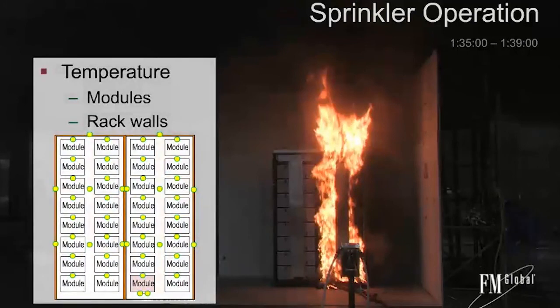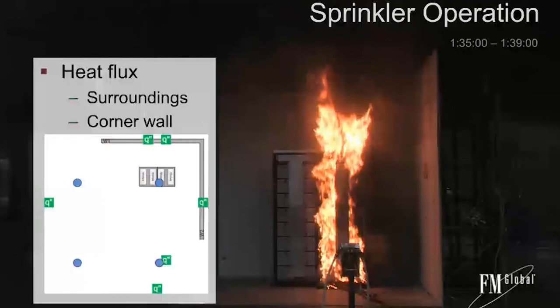To give you a sense of the density, here's an elevation view schematic of the picture you're seeing. All these yellow dots represent the location of a thermocouple. You can see them on each module, and you can see them on the rack walls. This will really help us understand how heat moves through the module, and also how reliable temperature measurements are within such a densely packed type of hazard.